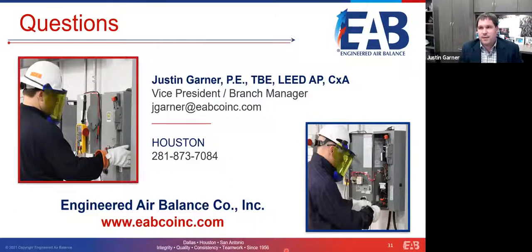And so my stance, and some might not agree with me, is that if you can safely do it, you should verify that measurement. But if you can't, then taking it off of the display of the VFD is certainly a viable option. And it's better than nothing at all. Just what we often say within our company is, if you do that, you need to note that we didn't measure it with our instruments, that we took that off the display of the drive itself. I hope that answers that person's question.